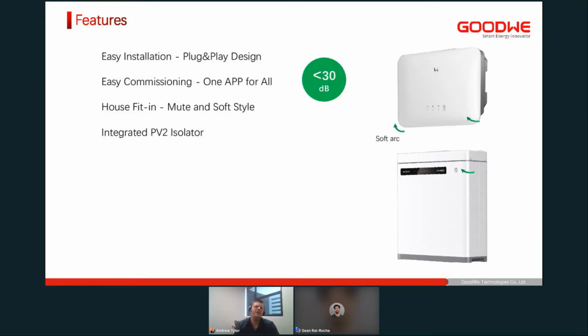So it's very familiar, very easy to do. It's the only way that you can ensure that the connection is correct. When you're using just an open terminal block, you may not screw it in correctly. There might be a loose connection, and that does take a little bit more time on site. So we prefer to have this plug and play design.